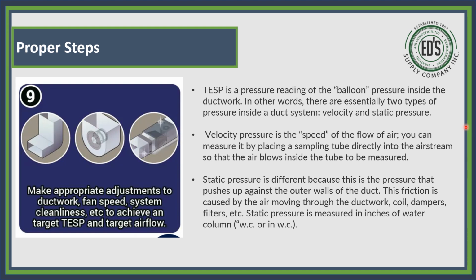If you look at the ductulator and you look at your friction rate, that's what that 0.10 or 0.08 that everybody sets their ductulator at to size their ductwork, that is not your static pressure. That is your friction rate. Friction rate determines velocity, and then your velocity and your friction rate will determine your static pressure. So you've got to understand that just because I set that ductwork at 0.10 doesn't mean my static pressure is going to be 0.1. Just because I set my ductwork at 0.08 doesn't mean my static pressure for my unit is 0.08. That's just a friction rate.